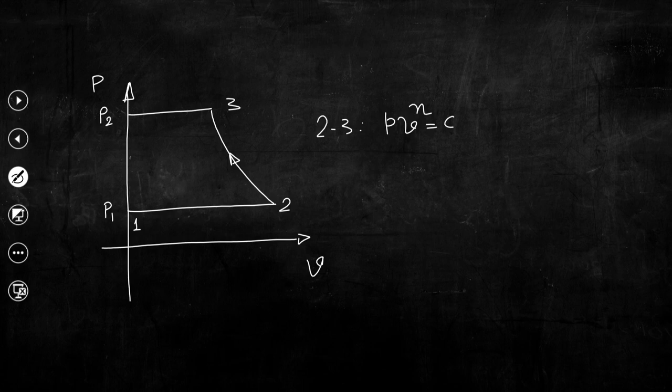If we increase the pressure using a single stage, there will be problems: reduction in volumetric efficiency, reduction in COP, more work input, and such a high rise in temperature at the end of compression that it will have a detrimental effect on the mechanical components of the compressor.